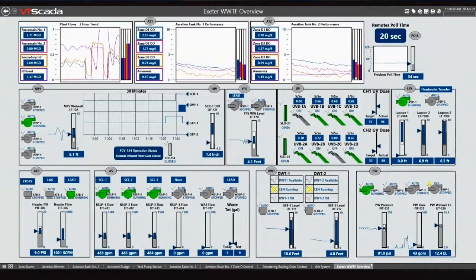But the real power is we also have the ability to create those same data structures within the PLC programming. What we have been able to do is create a data structure in VTScada, create a data structure in the PLC, and then through the power of using expressions, linking through the parent-child relationship of the tag database, linking common tag names through expressions that actually directly address the PLC I/O.